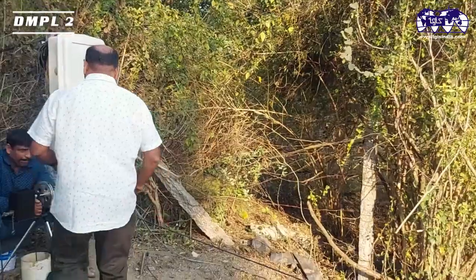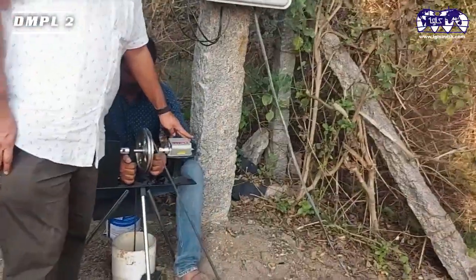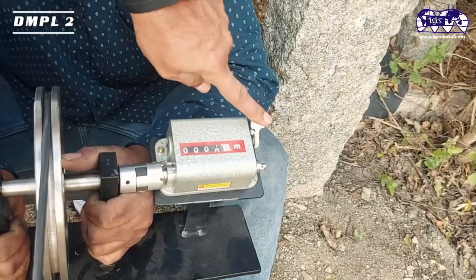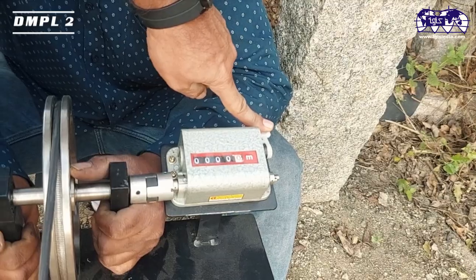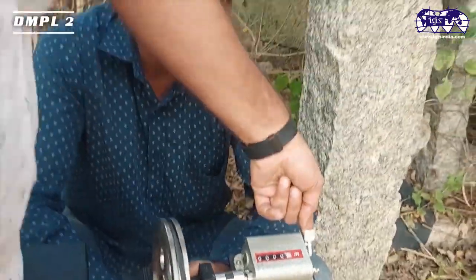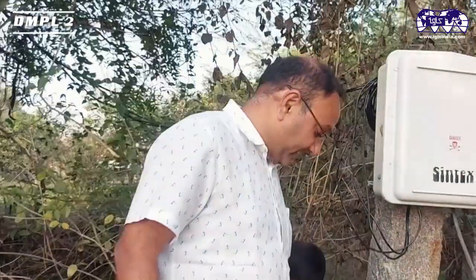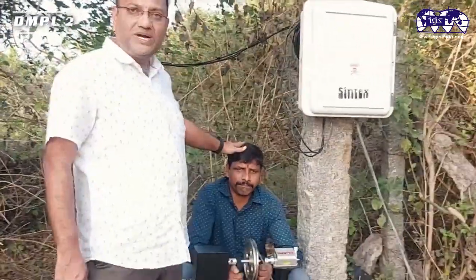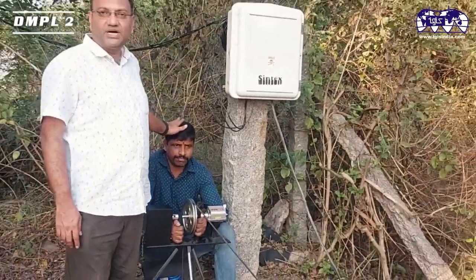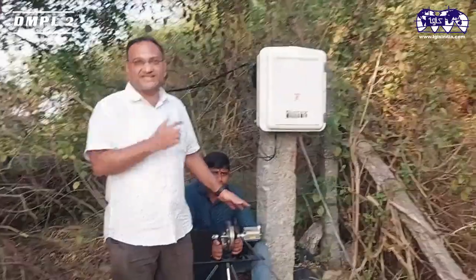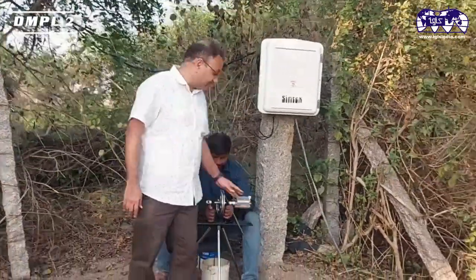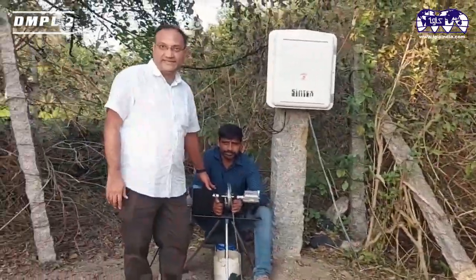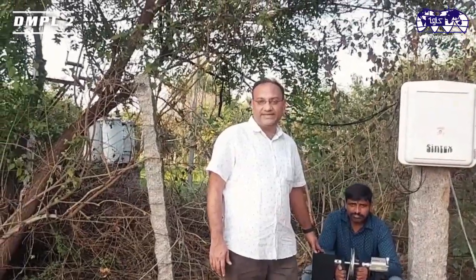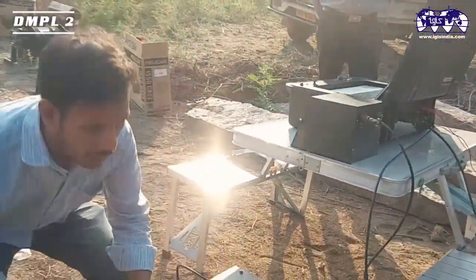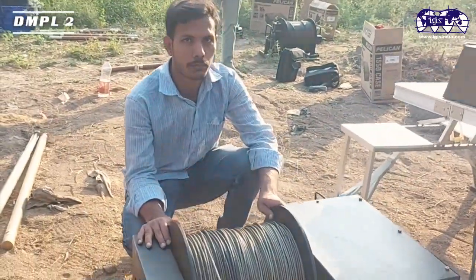Now I am setting this to 0. As always, setting it to 0 is the downward direction this way. Never do it in the other direction. It would damage the connector. And it is always advisable to have one person holding it, because there would be a lot of stress on the cable and there is a possibility of it slipping. That's the reason he is holding it here and keeping it accordingly. Similarly, one more person is near the winch to release the cable.